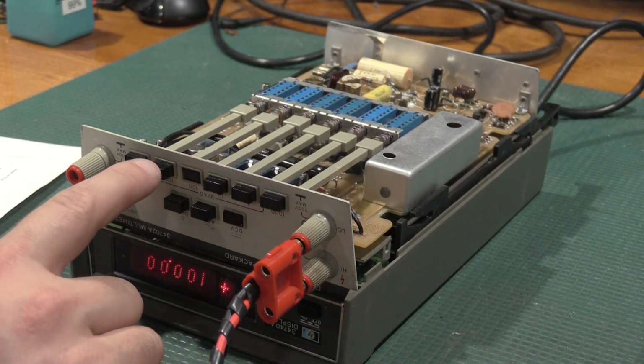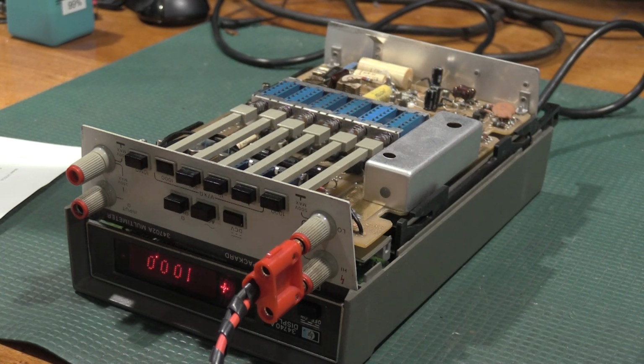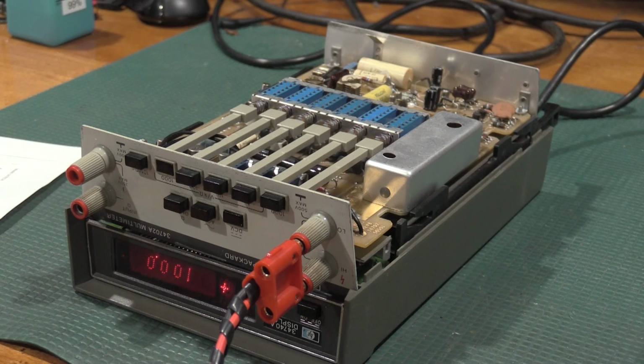There's 100. We'll preliminarily set the 1000 volts, although preliminary set it to 100 volts. And we'll check the 1000 volt range next. Now that we got 100 volts DC on there, we're going to turn this source off before we start touching the connections.